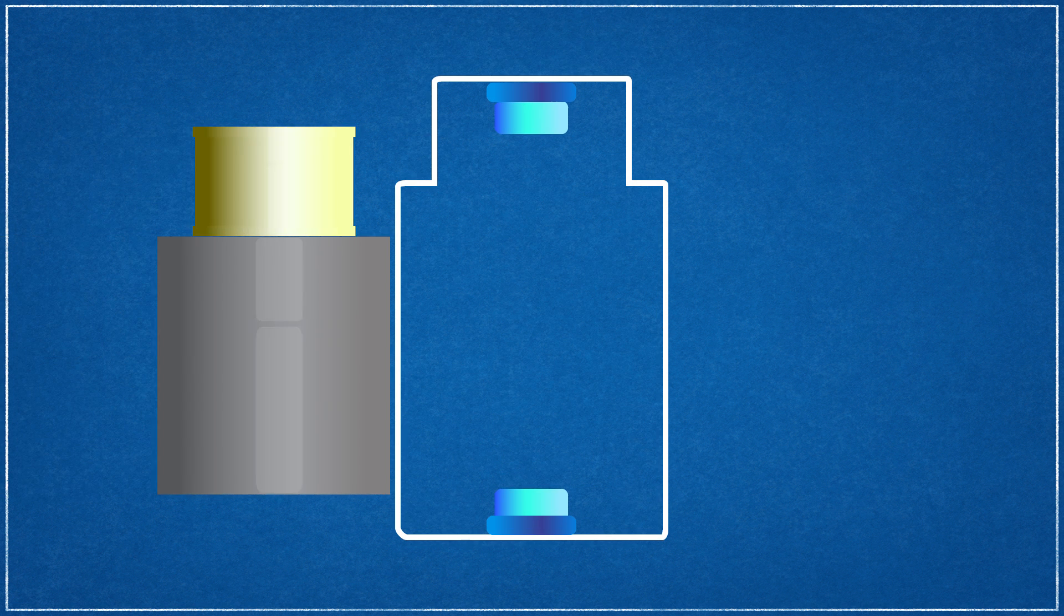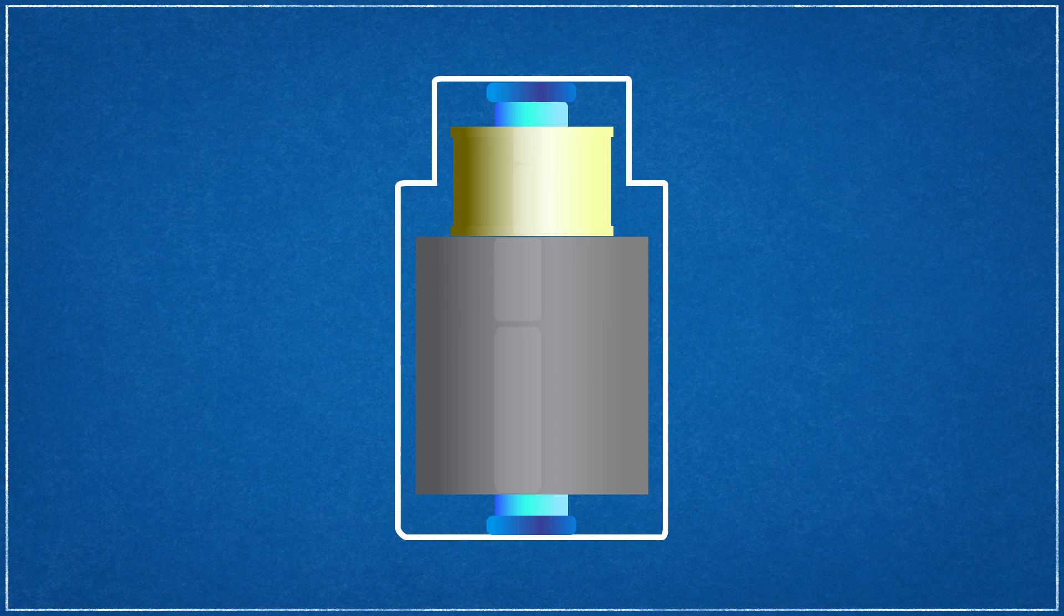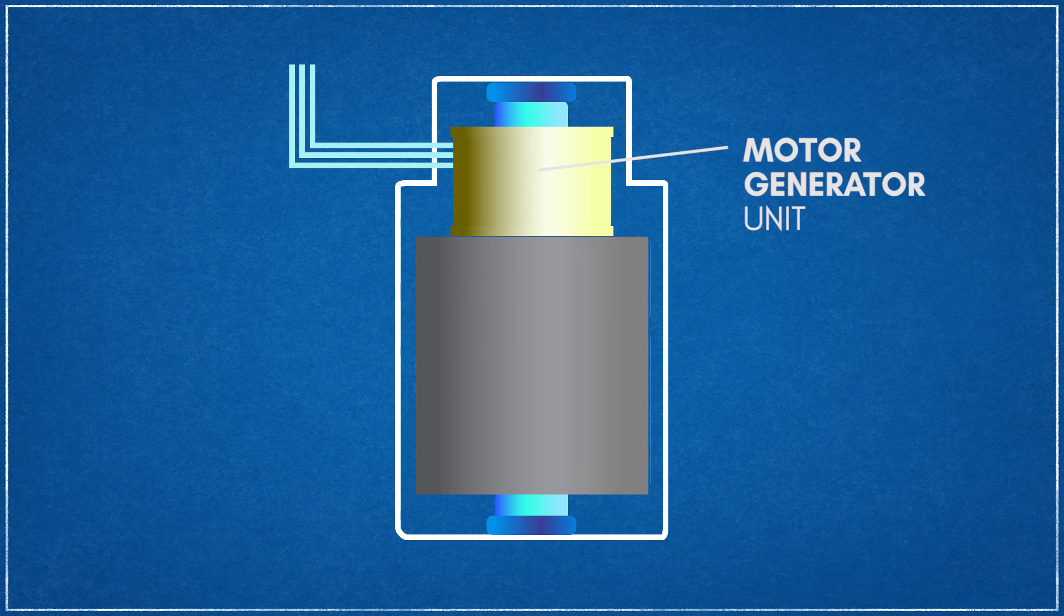The input energy to a flywheel energy storage system is drawn from an external electrical energy source such as a power grid. The flywheel speeds up as it stores energy and slows down when it's discharging to deliver the accumulated energy. The rotating flywheel is coupled to an electrical motor generator unit that performs the interchange of electrical energy to mechanical energy and vice versa.